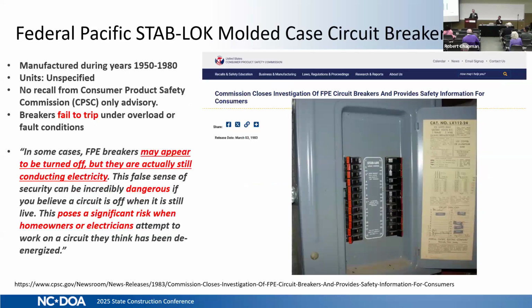Another is circuit breakers. If anybody's ever heard of Federal Pacific, they're notorious. It's an obsolete manufacturer that no longer exists, but they produced breakers, and when you turned the breaker off, it was still allowing current to flow. The supplied load was still energized. So that's another reason, and there are other manufacturers whose equipment can fail, right?